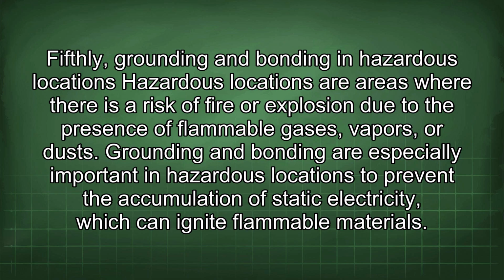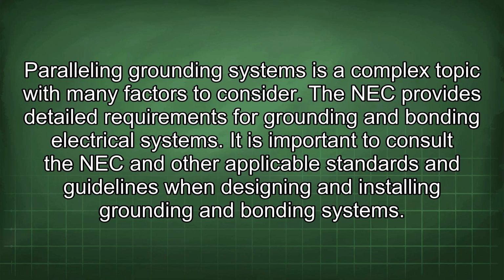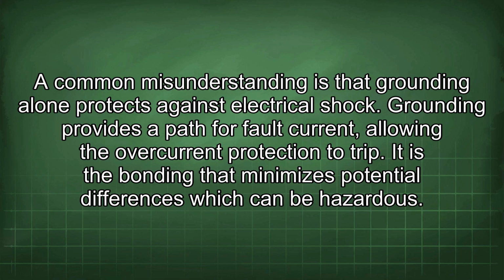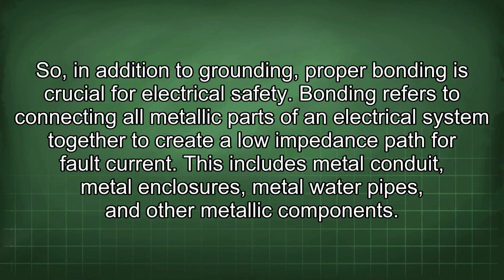Parallel grounding systems is a complex topic with many factors to consider. The NEC provides detailed requirements for grounding and bonding electrical systems. It is important to consult the NEC and other applicable standards and guidelines when designing and installing grounding and bonding systems. A common misunderstanding is that grounding alone protects against electrical shock. Grounding provides a path for fault current, allowing the overcurrent protection to trip. It is the bonding that minimizes potential differences which can be hazardous. So, in addition to grounding, proper bonding is crucial for electrical safety.